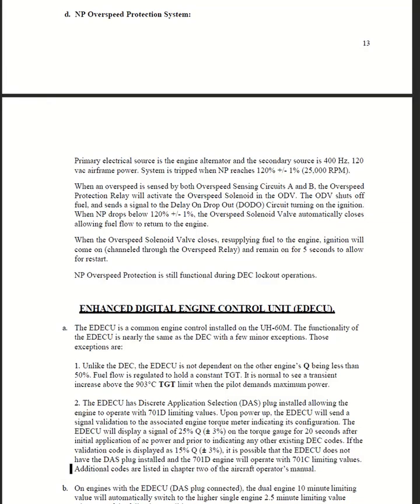When NP drops below 120%, plus or minus 1%, the overspeed solenoid valve automatically closes, allowing fuel flow to return to the engine. When the overspeed solenoid valve closes, resupplying fuel to the engine, ignition will come on, channeled through the overspeed relay, and remain on for 5 seconds to allow for restart. NP overspeed protection is still functional during DEC operations and lockout.